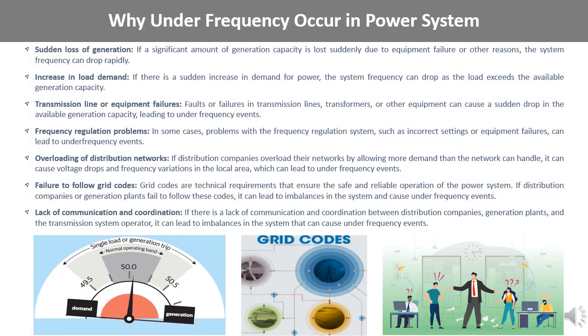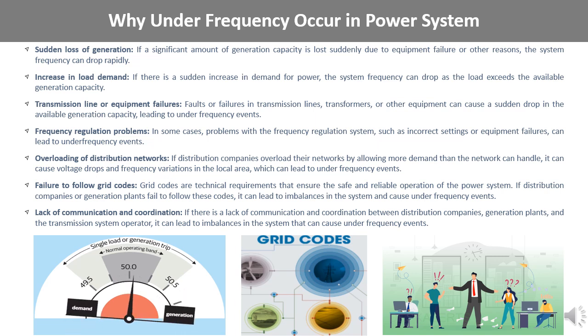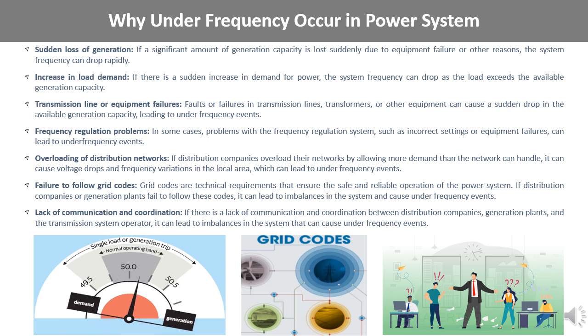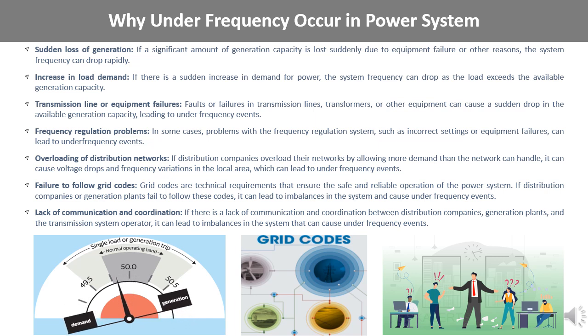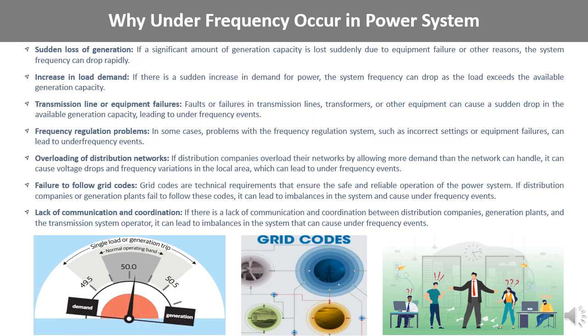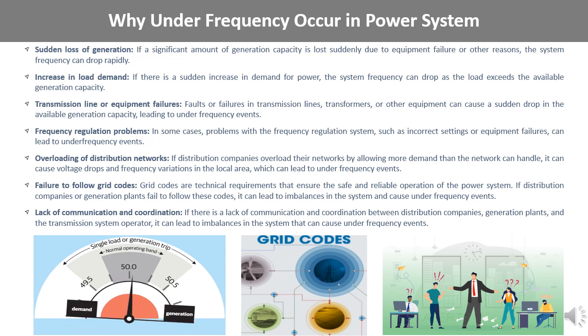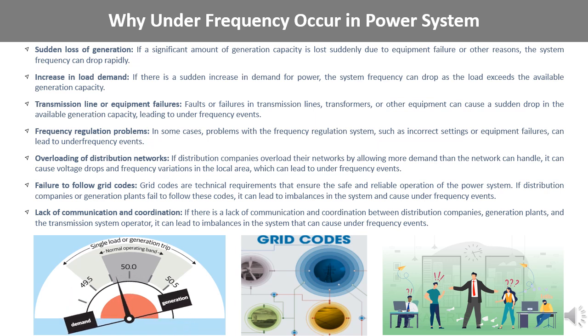In the world of power systems, under-frequency events can be a significant concern. Let's explore some of the common reasons why under-frequency events occur. One common cause is a sudden loss of generation, which can occur due to equipment failure or other unforeseen circumstances that result in a significant reduction in available generation capacity, causing the system frequency to drop rapidly. Another cause is an increase in load demand — if there is a sudden spike in demand for power, the load can exceed the available generation capacity, causing the system frequency to drop.